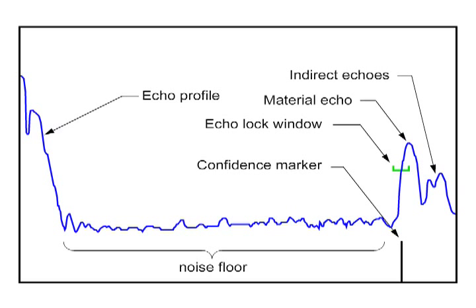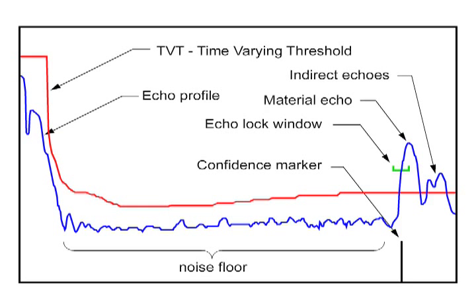Finally, we have this red line. The red line is our dynamic TVT curve. The TVT or time varying threshold curve is a mathematically constructed curve to help select the true material echo.